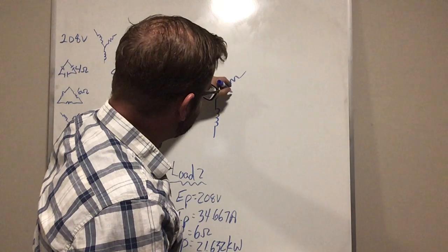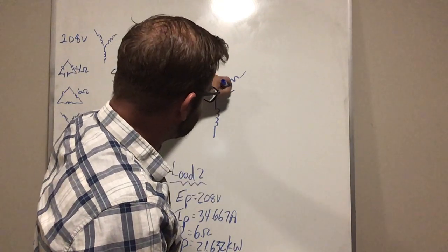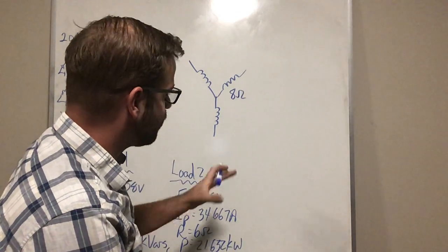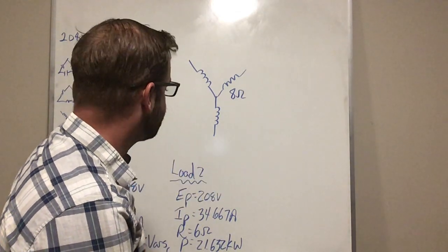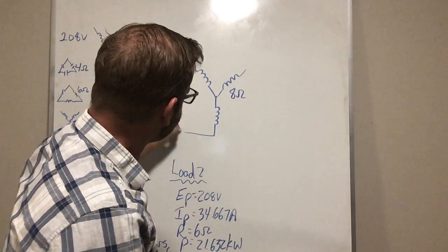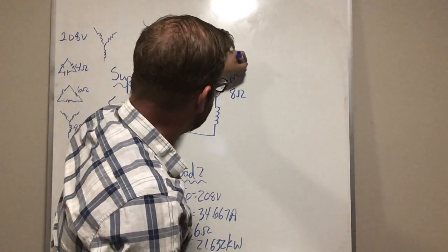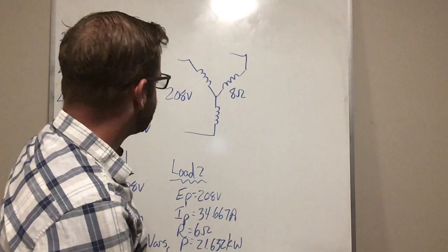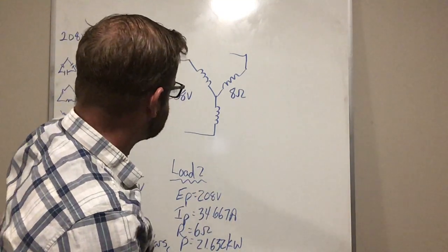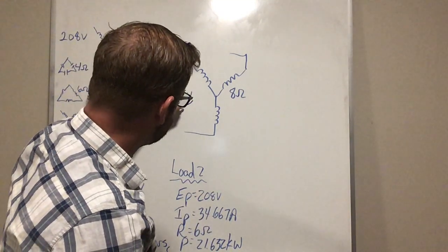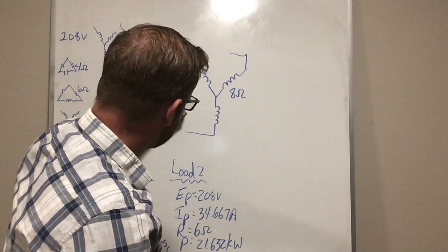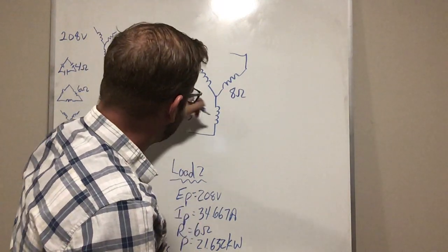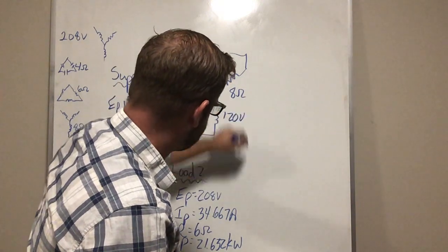And obviously you'll have all the information on yours. I'm trying to do it this way just so I have a little more room and it doesn't get quite as crowded on the page. We knew that we, again, have 208 volts for our line voltage, which means that we're root 3 smaller, so divide by root 3, or divide by 1.732, to give us 120 volts per phase.